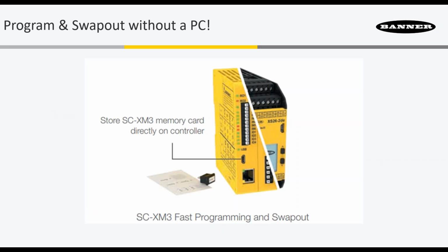It has a lot of power, a lot of functionality. And the other thing that we learned when we were talking to customers that were using safety relays is that what they really like about them is it's a mechanical installation. I can take my relay, I can plug my device into it, and it's done. As long as I select the right relay, that's one of the challenges. But with a controller, they said the last thing I want to do on these machines is have to get a PC out and program the machine when I build it, or when it goes to the end user and they have to eventually swap it out. I don't want to get a call at 3 a.m. from the maintenance worker to go and figure out how to program it. So we took that back to our R&D team and developed a solution for that.